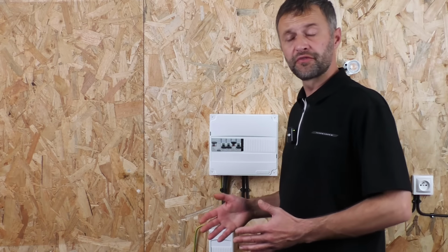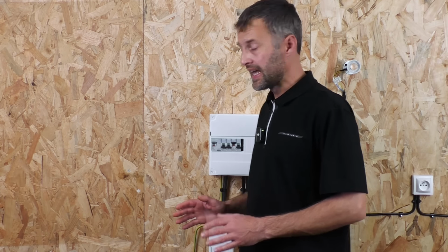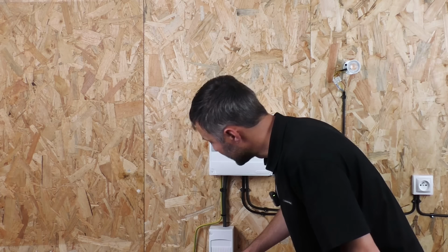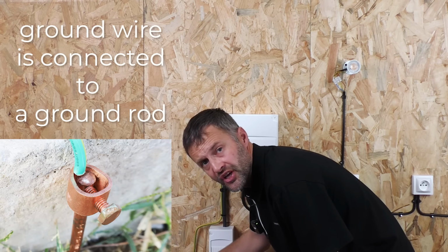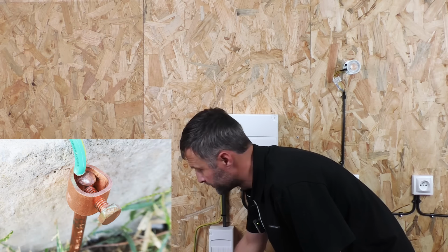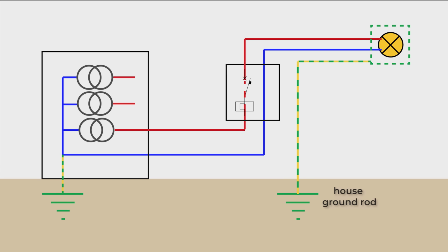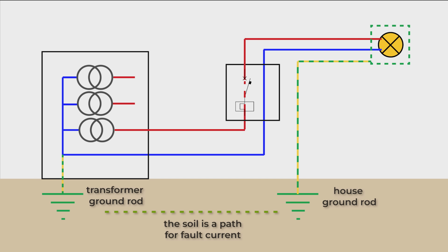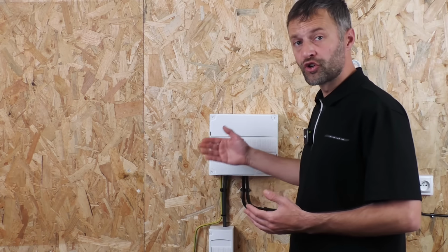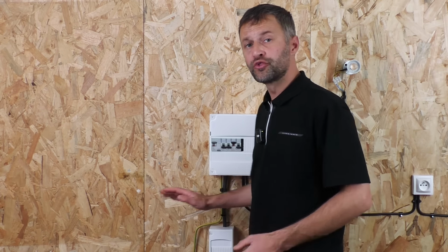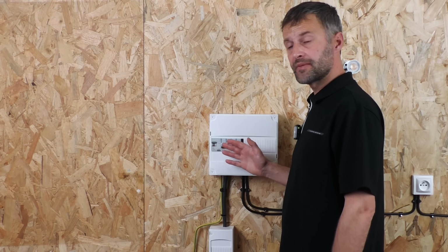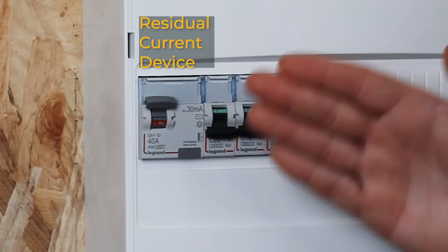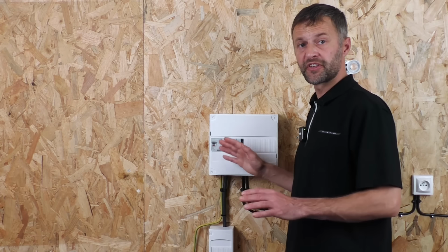Now, in some countries, like here in France, another type of grounding system is common. Instead of being connected directly to neutral, the ground wire is connected to a ground rod just outside your house, so it's connected to the soil. From there, the fault current can travel through the soil itself to the transformer, where you have another ground rod which is connected to neutral. But because soil is a lot less conductive than copper wire, the fault current may be too low to trip the circuit breaker. That's why these systems rely heavily on another device called an RCD, or GFCI in North America. It's the same thing, different name.